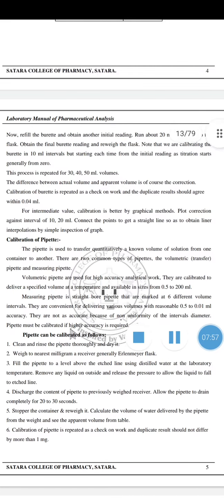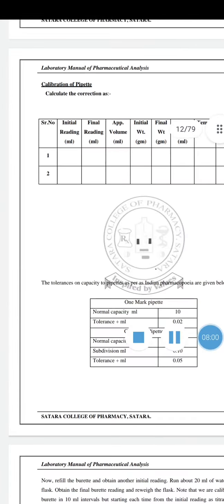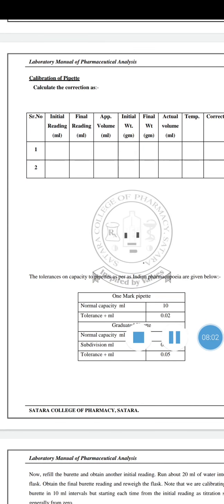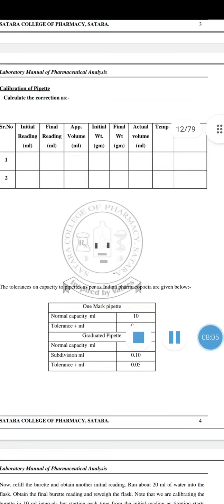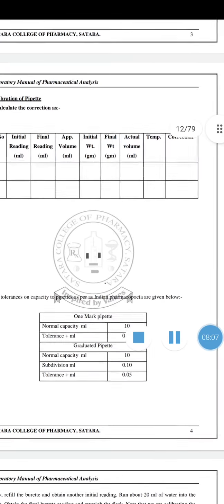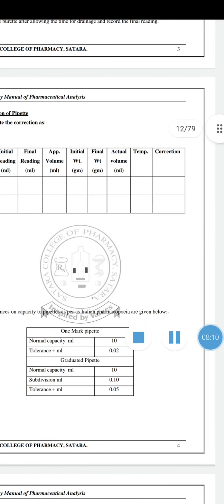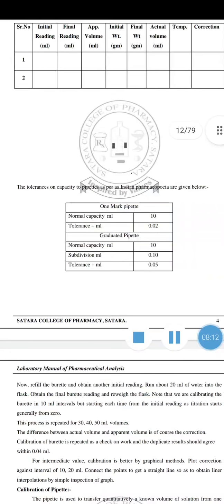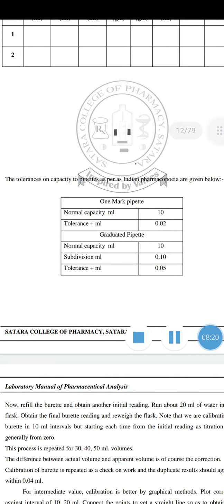And then next is the calibration of a pipette. This is an observation table. Calibration of a pipette: calculate the correction, as there is initial and final reading, then apparent volume, initial, final, weight, actual volume, then temperature, correction, and the tolerance on capacity of pipette as per the Indian Pharmacopoeia as given below. For a one mark pipette the nominal capacity is 10 ml, tolerance plus or minus 0.02 ml, and for a graduated pipette the nominal capacity is 10 ml, subdivision 0.10 ml, and tolerance plus or minus 0.05 ml.